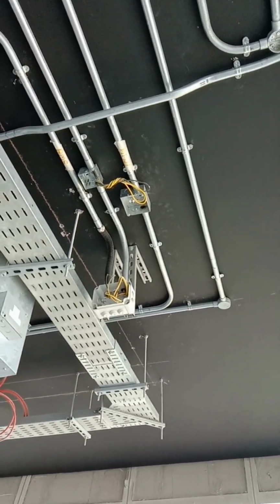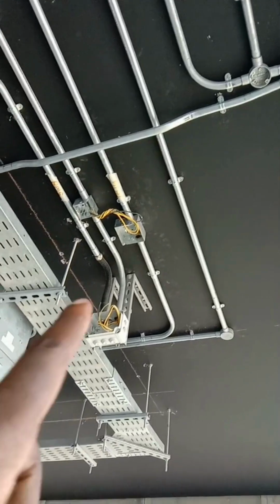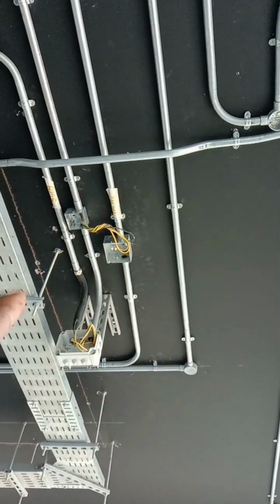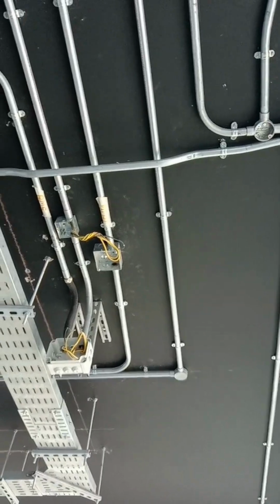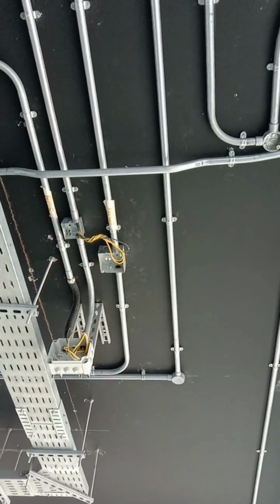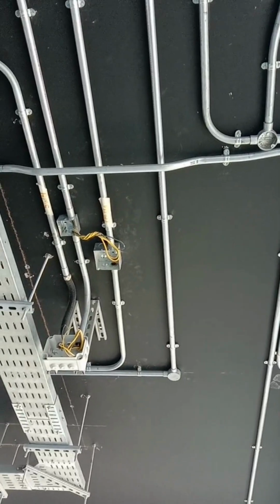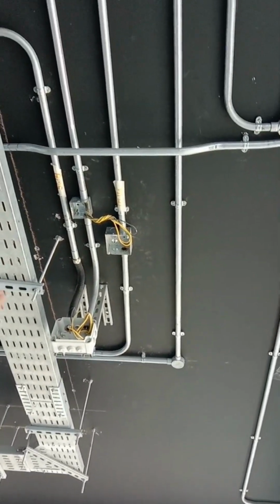So basically what we'll do here is just pull the cables. Once we're done with the cables, we start testing for continuity as well as insulation resistance. Once that's done, we can start termination and then commissioning of the system.